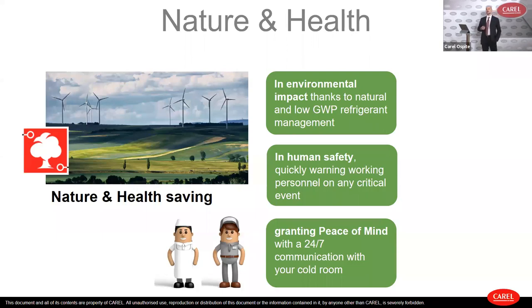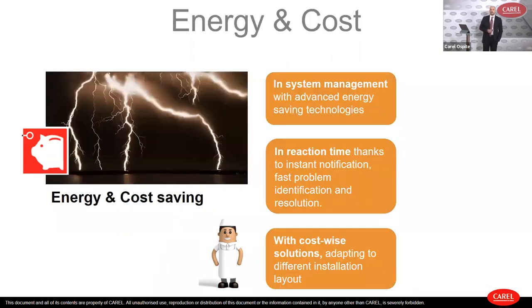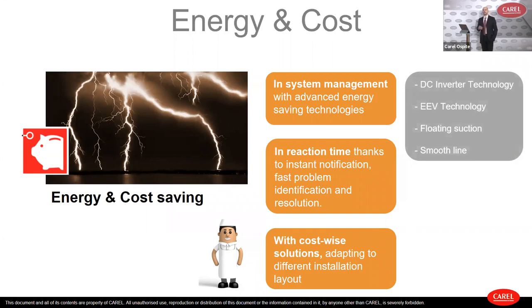Also very important: peace of mind. The end user going on vacation can be absolutely confident that his remote system will warn him — or directly warn his service company — to act on his cold room. This is achieved by exploiting alarms, notifications, and remote monitoring. On the energy and cost side, we can save energy thanks to advanced system management, using DC technology on the condensing unit, electronic expansion valves on evaporators, floating suction, smooth line — algorithms that grant increased energy savings.